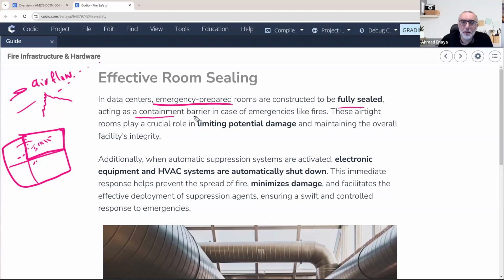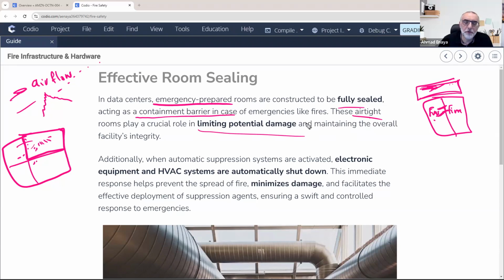To do that, we need to have some sort of containment barriers between rooms. In a hospital, you always see fire-rated doors between different departments, and even in houses, the door that connects the house to the garage is typically fire-rated, which means they don't allow fire to go through. And there should also be something similar in the plenum. There should be something to block the air between these two spaces, to consider them sealed. It is not enough to have the door fire-rated. They should be sealed even in the plenum, above or below, to make sure the air doesn't flow between these two locations. So this is what we call room sealing. It is mainly to have airtight rooms to limit the potential damage and to control the spread of fire.